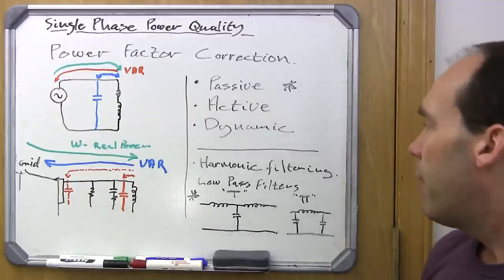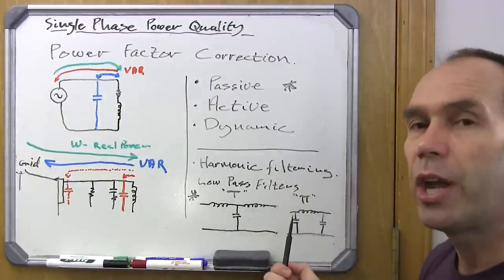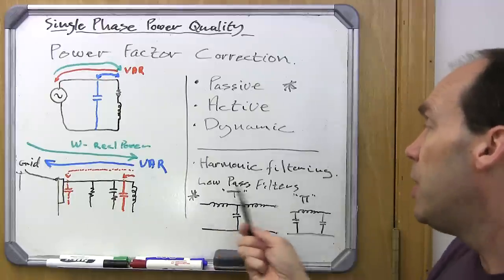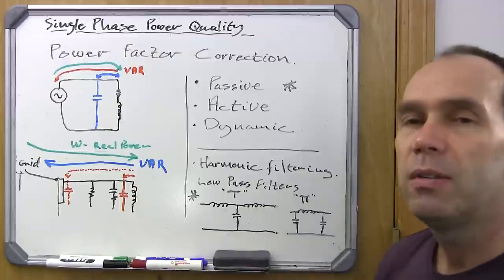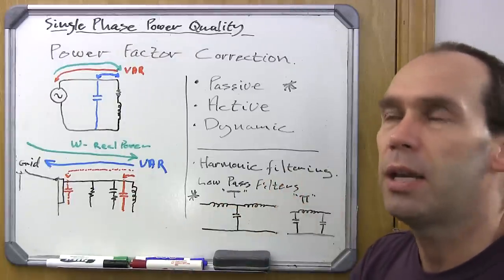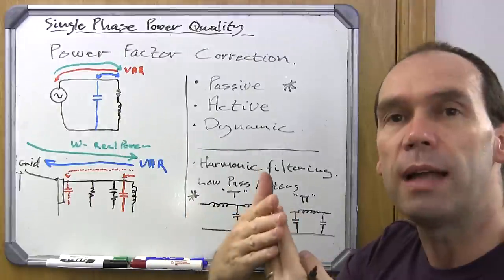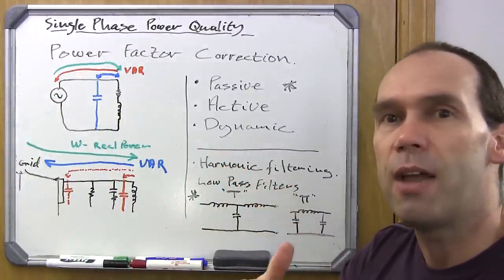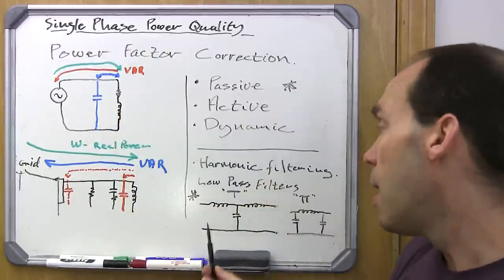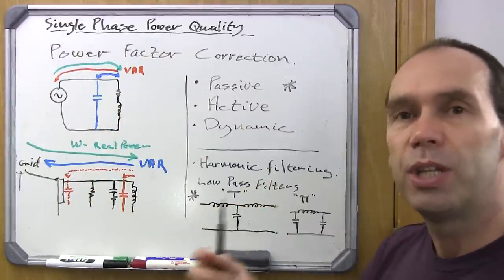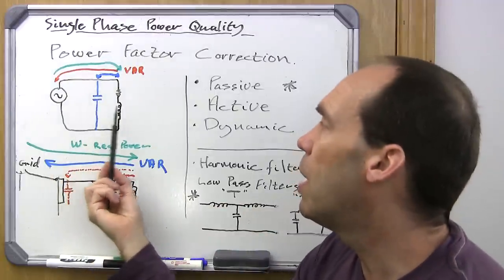Regarding harmonic filtering, this passive example isn't going to change — you set it up for a certain amount of harmonics. These are low-pass filters: you get T filters and pi-shaped filters, which are set to allow lower frequencies through. If you've got 60 Hz mains, your harmonics are multiples of that and are higher. Put in a low-pass filter allowing everything below 100 Hz to pass, and you'll start filtering out your second, third, fourth, and fifth harmonics. You do also get dynamic filtering that adjusts for various frequency requirements.